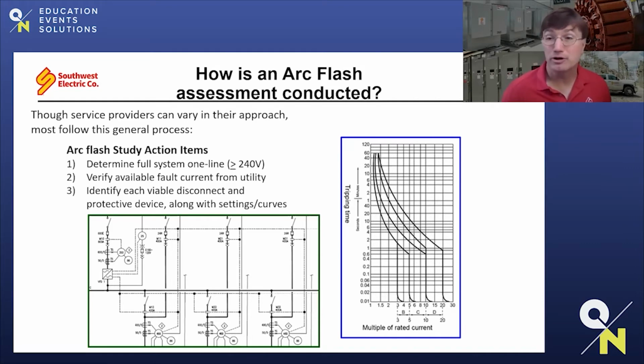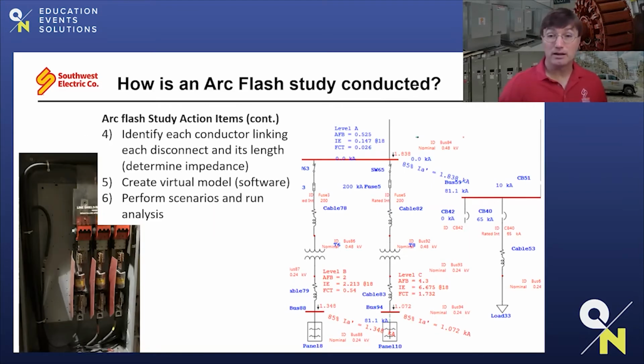But this takes an extraordinary amount of time to verify all this equipment. Oftentimes, this equipment may be energized while this data is being collected, and individuals have to be suited up in order to obtain this information. Once all this is documented, this is fed into a computer model. As we're documenting this data into a model and building this representation of the electrical system, we're able to determine the amount of impedances and characteristics of that system, and then run numerous scenarios where we simulate an event at every single electrical bus throughout the system.